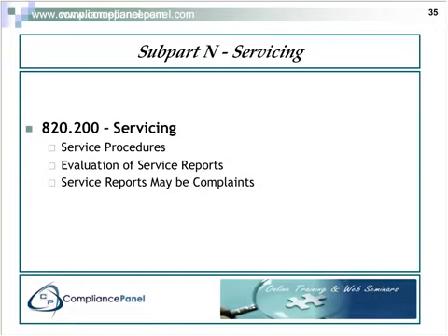Analysis of service reports is also important in case there's been an adverse event which triggered the service call, in which case that would become a complaint and would be required to follow the complaint handling procedures. In some cases, it could be inferred that any warranty service required can constitute a complaint as the device failed to meet its reliability specifications. So you need to weigh how these service calls affect the complaint handling process.